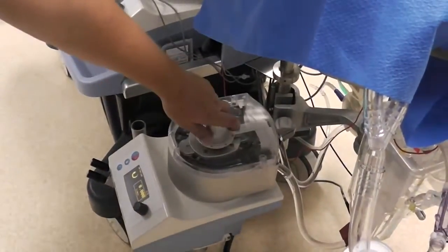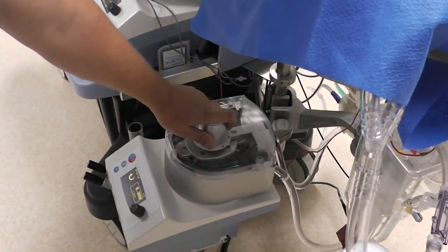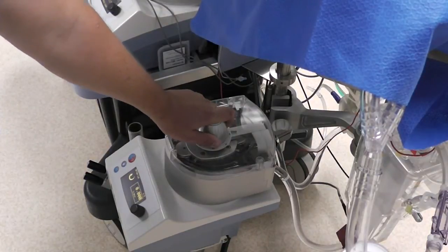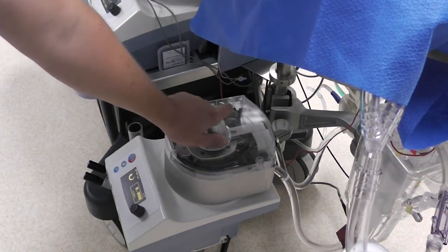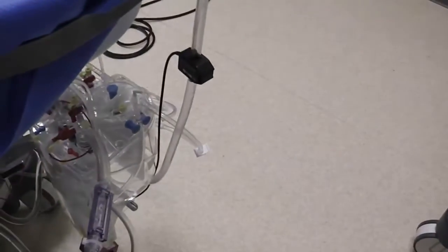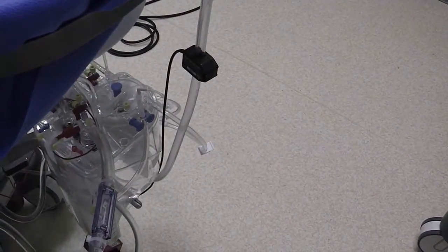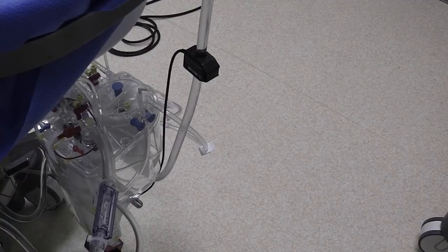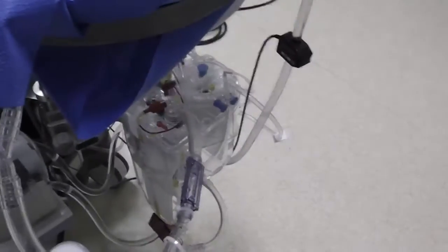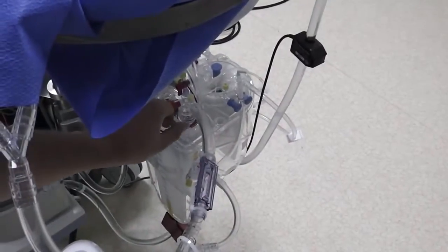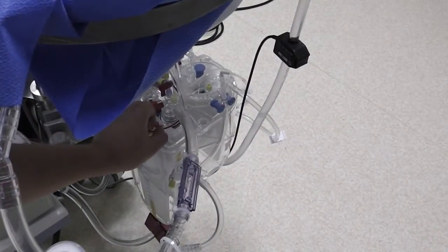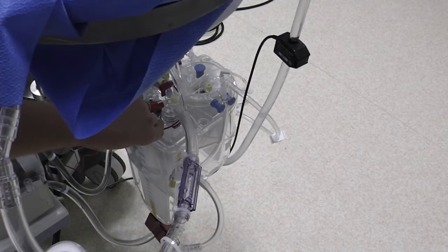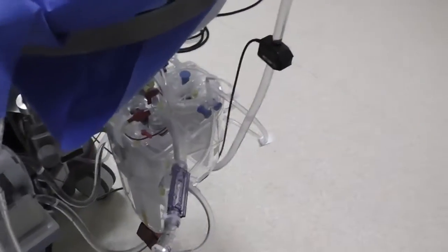So to adjust this occlusion, come over to the pump here, and to tighten it, which is what we need to do, we are going to rotate this counterclockwise. Which seems kind of counterintuitive, but that's the way it needs to go. I'm going to actually give this one more turn to bring it up a little bit. And if you go too far, you can open up any one of your purges, such as on the manifold here. You can just open this up, and as long as you haven't gone way far into the tubing inside the basket, it will bring that back down.